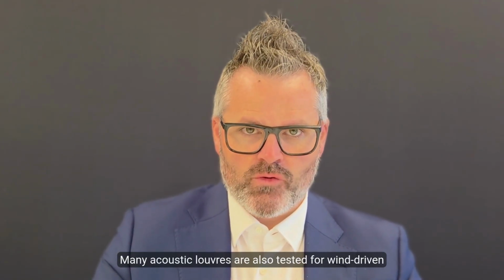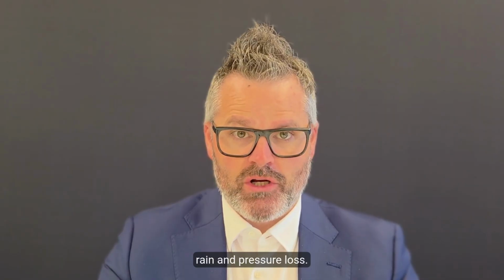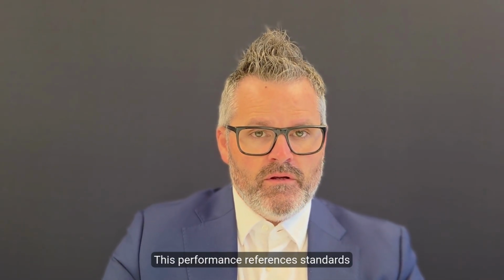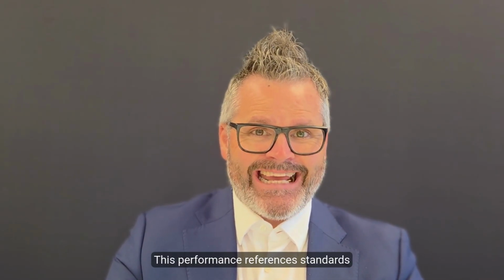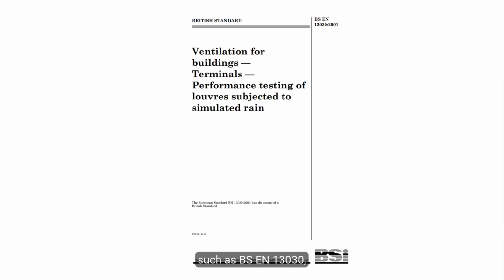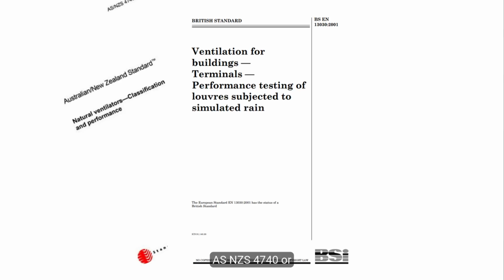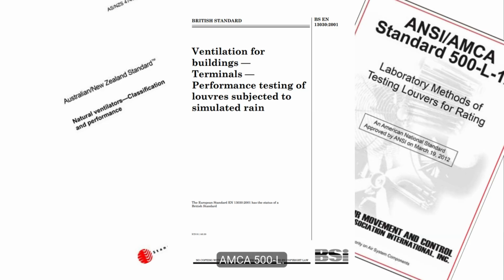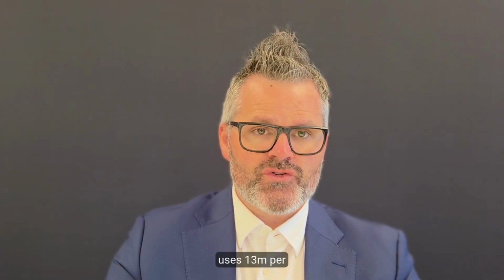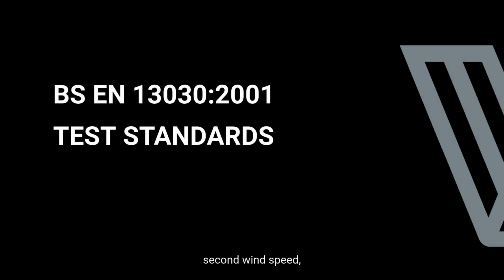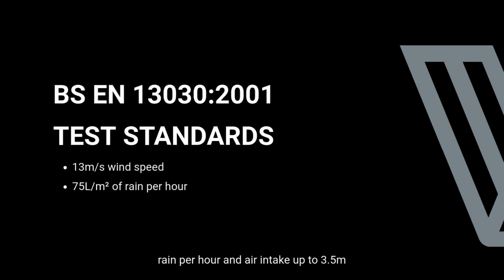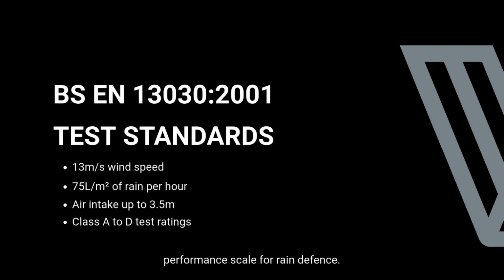Many acoustic louvers are also tested for wind-driven rain and pressure loss. This performance references standards such as BS EN 13030, AS/NZS 4740 or AMCA 500-L. BS EN 13030:2001 uses 13 meters per second wind speed, 75 litres per square metre of rain, and air intake up to 3.5 meters per second, and the familiar Class A to D performance scale for rain defence.